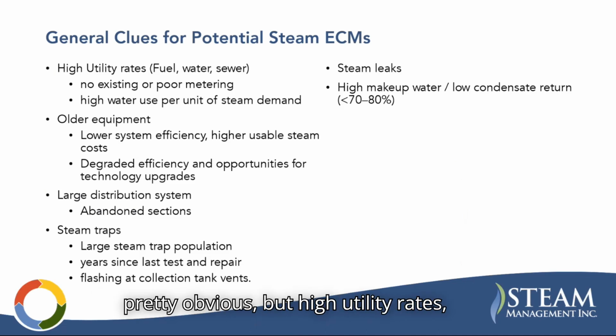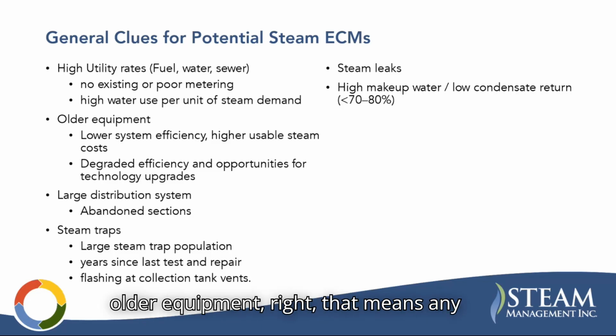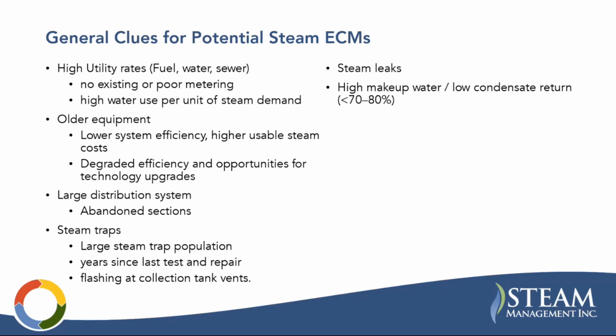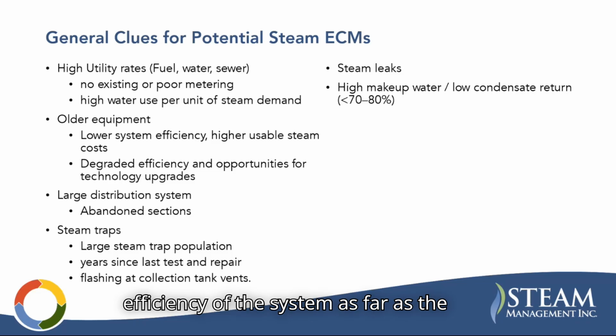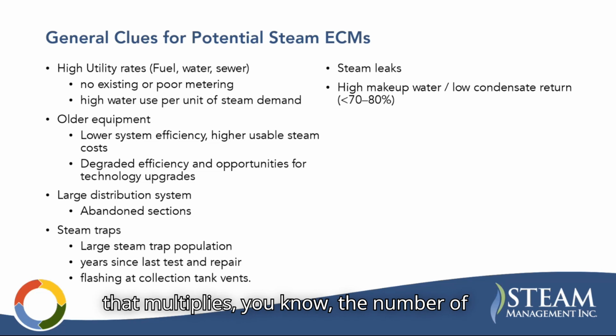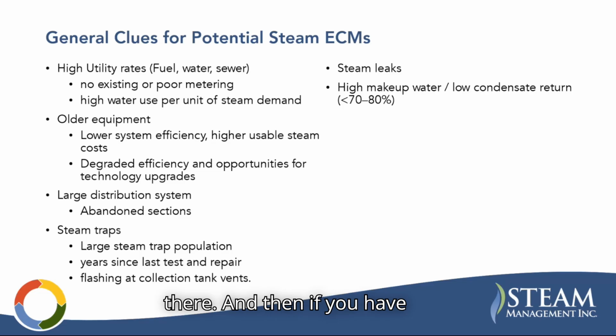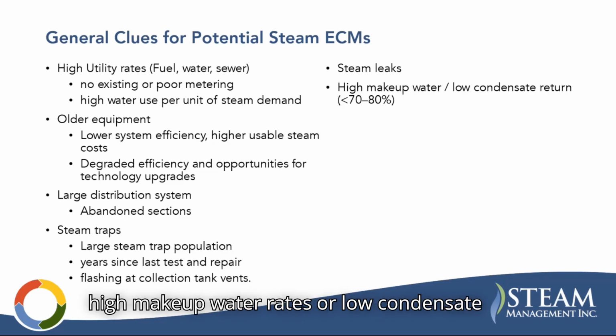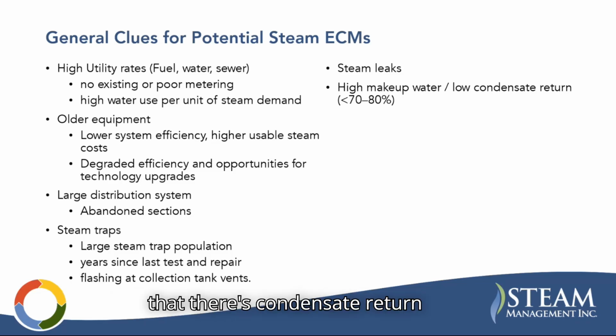General clues, some of these are probably pretty obvious: high utility rates, no existing or poor metering, high water use per unit of steam demand. If the system just has older equipment, that means any amount of steam or heat that we save is then multiplied by the poor efficiency of the system as far as the fuel cost. If you have a large distribution system, you're likely to have abandoned sections, piping leaks, insulation deficiencies, and also likely a large steam trap population, and that multiplies the number of failed traps and the opportunity there. And if you have high makeup water rates or low condensate return, that's usually going to indicate condensate return improvements, or just a low system efficiency, and it's in your best interest to try to conserve some steam.